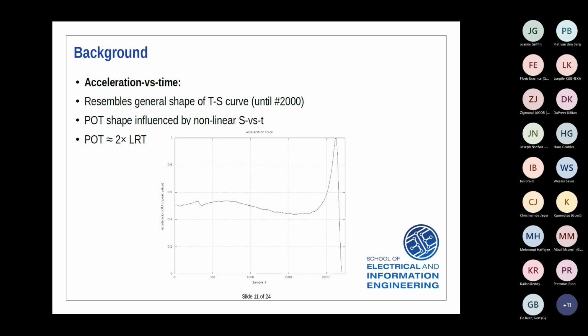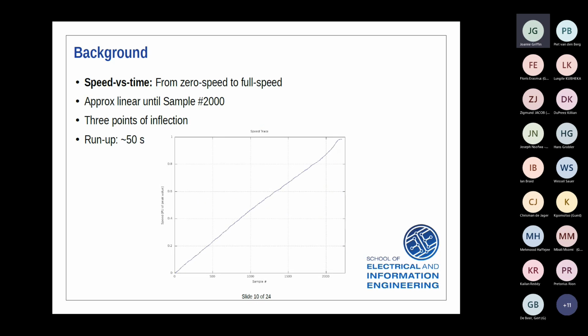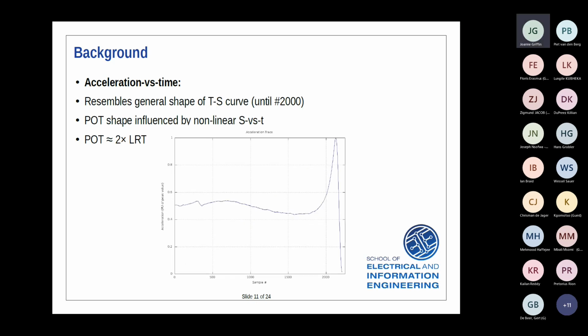Okay. Just a note I've made here, the pull-out torque shape is influenced by the nonlinear speed versus time. So in the previous graph, we see this very steep climb here, right towards the end. And you can see that's resulted in this very rapid increase in torque. In fact, here the pull-out torque is roughly 2 times the locked-rotor torque. So locked-rotor torque is about 0.5. Pull-out torque is, I've just called it 1 in this example.